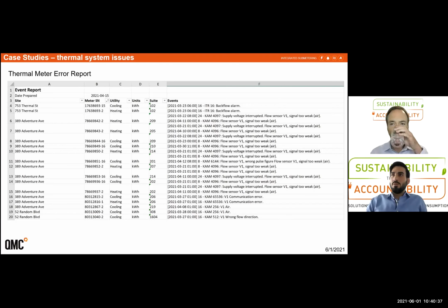We're seeing a lot of errors here as power disruption for the flow meter part of the thermal meter. And this is shown here as a communication error, or the supply voltage interruption. When there's no power provided for the flow meter to make the measurement, there would be no energy recorded on the calculator.